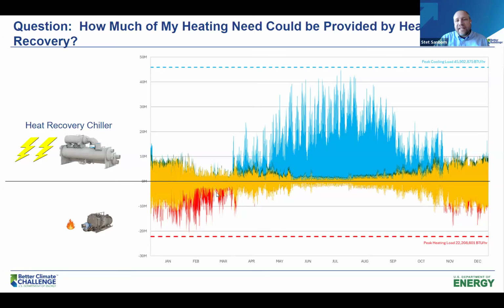And so all that yellow in this graph represents all the hours and how much load a heat recovery chiller in this commercial building could have offset the heating load. So now, without putting in brand new spanking heat pumps just for heating, I've replaced my chiller, and I've accomplished an 80% reduction, 90% reduction in the greenhouse gas associated with heating. So instead of just focusing on heating, let's focus on heat recovery first, and maybe leave your boiler in place both for backup or to meet those few hours that aren't met.